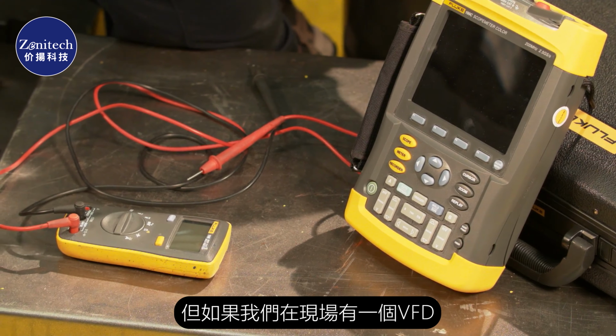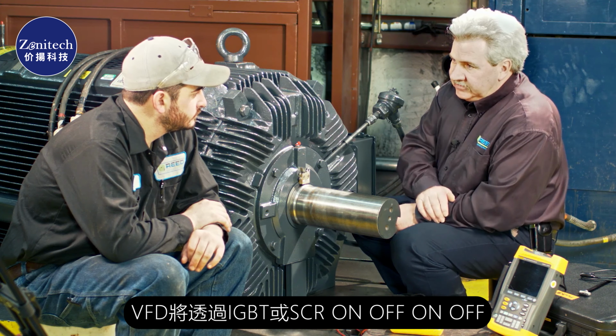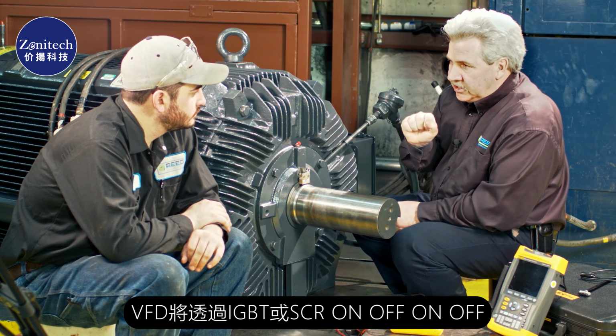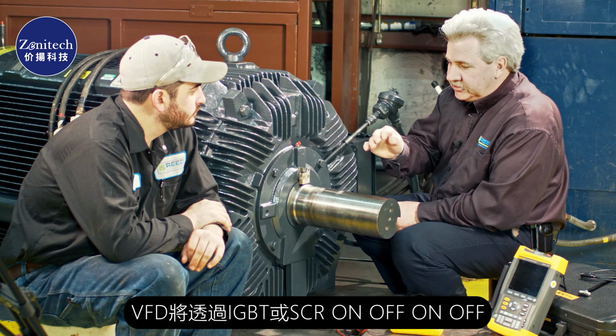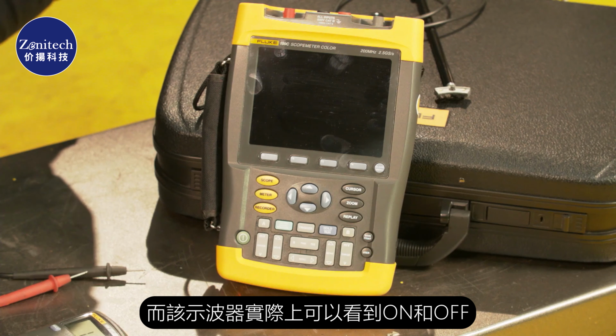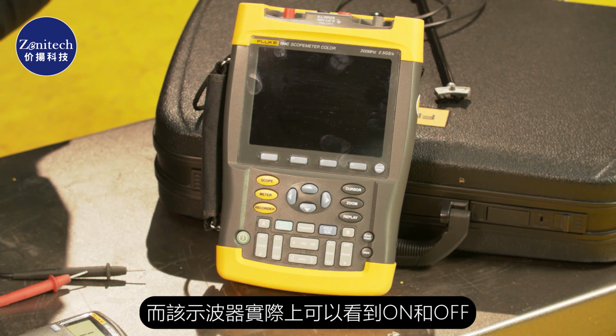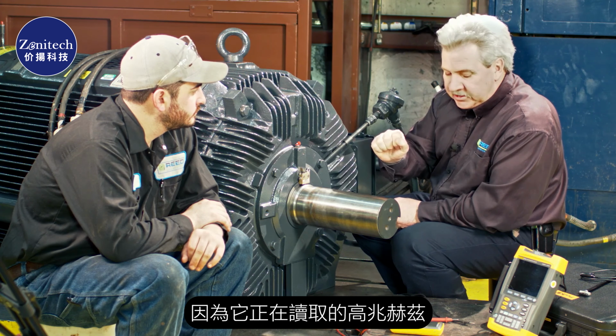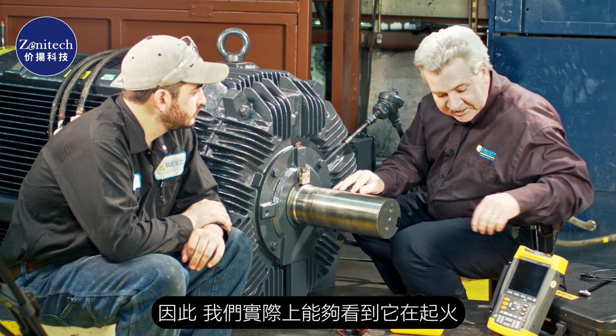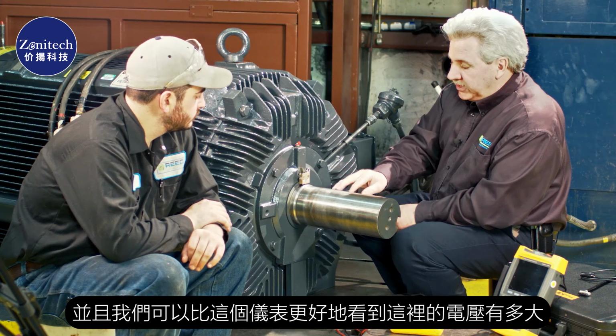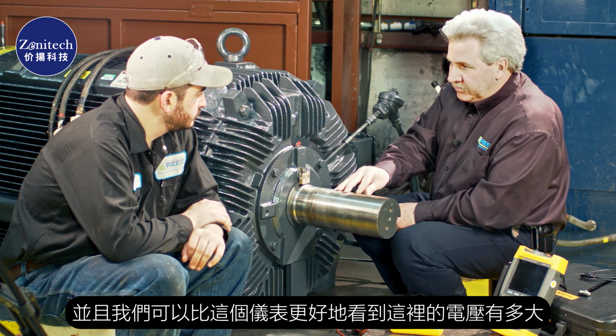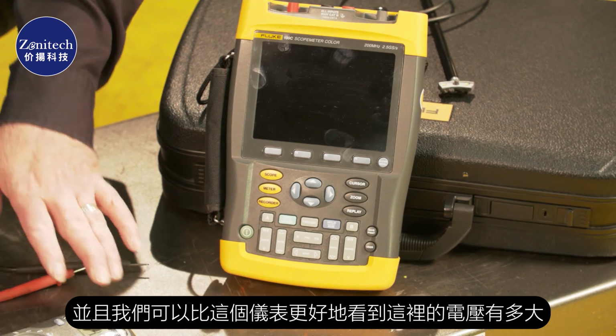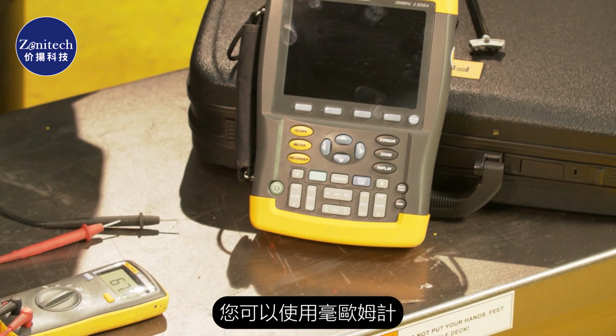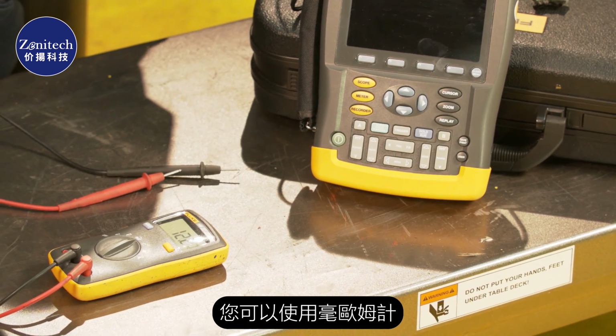But if we have a VFD out in the field, the VFD turns on, turns off, turns on, turns off by the IGBTs or the SCRs. And this scope can actually see the on and off because of the high megahertz that it's reading. So we're actually able to see it firing. And we can see how big a voltage we have in here, much better than with this meter. But for standard shop purposes, you can use the milliohm meter.